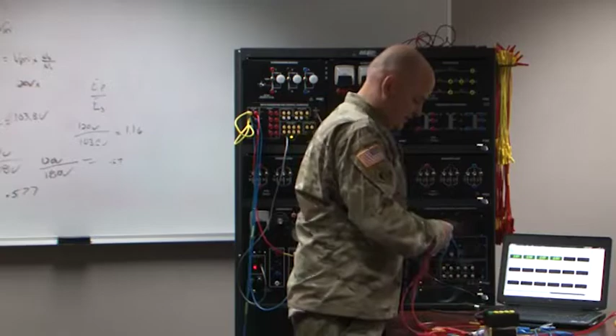Now we're going to talk about transformers in parallel. What happens if I take this one conductor and ask, how many amps can I put through it? That's a function of the material science of the conductor, the rho value, whether it's copper or aluminum, the resistivity, and the length. How much current can I put through this? I'll get a value based on that science, or I could read it from charts in the NEC, like tables 310.15 or similar.